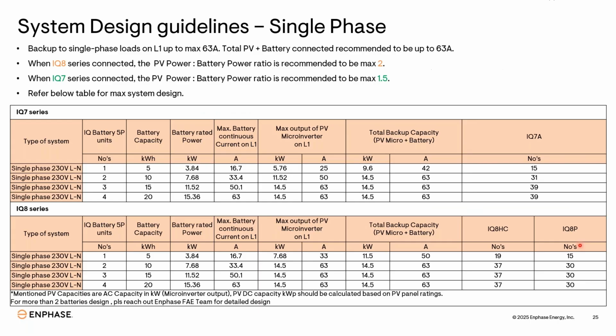Let's move to our system design guidelines. For a single phase, you can go up to twice the capacity of the battery for the IQ8 series and 1.5 times for the IQ7 series. So if you are using an IQ7 series and you have one single battery, one single battery is capable of 5 units, and the output power is 3.84 and the current will be 16.7. So the maximum output PV power for L1 is allowed 3.84 multiplied by 1.5, and you are going to get 5.76. So maximum you can go up to 5.76 kilowatt of PV on the AC side. I'm talking only about AC sides.